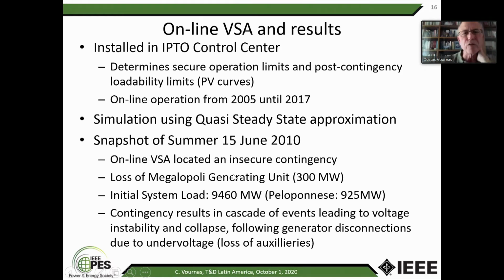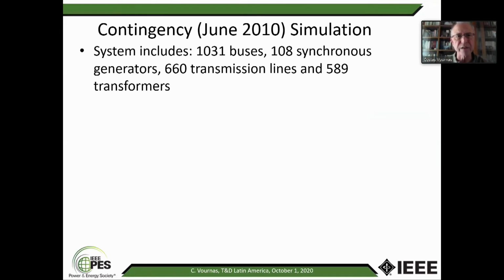And as I said, on June 15, 2010, we had this insecure contingency, which is the loss of one large unit, a 300 megawatt thermal unit, while the system load was close to 9,500 megawatts. And in Peloponnese, we had something less than 1,000 megawatts. And the contingency simulated never happened, okay? So that's what security means. Security assessment means I want to know what if. So if on this date, June 15, 2010, at about 1-2 p.m., I lost this unit, then I would have had a collapse. This never happened, but in simulation, we know that there was a dangerous contingency.